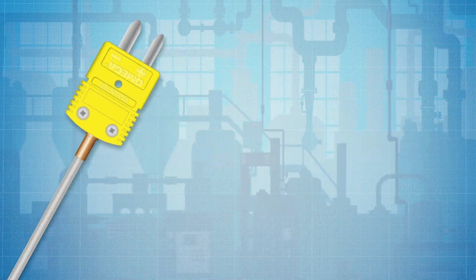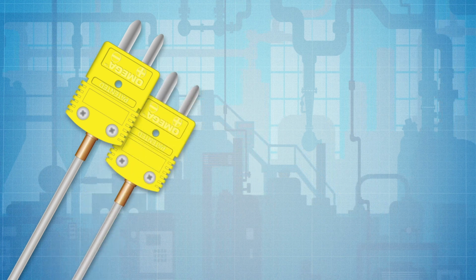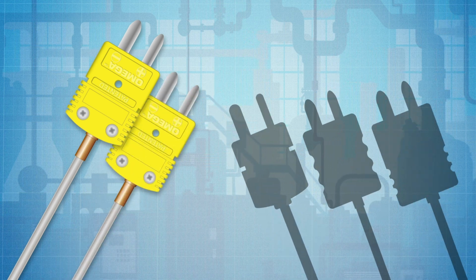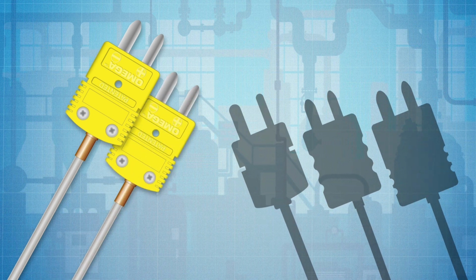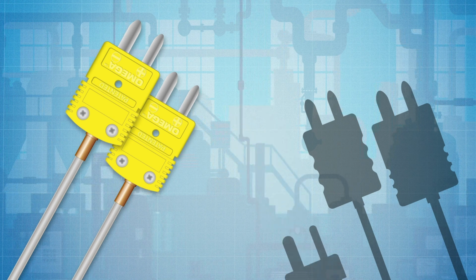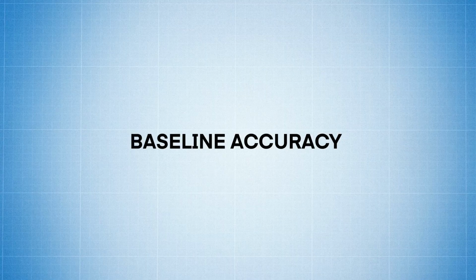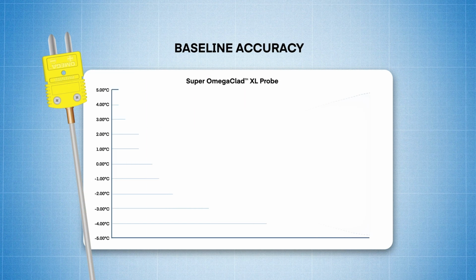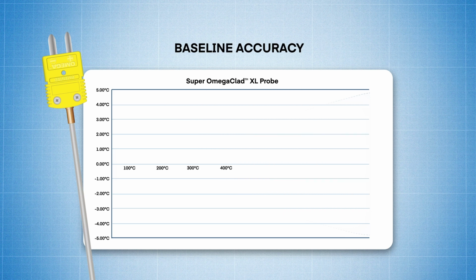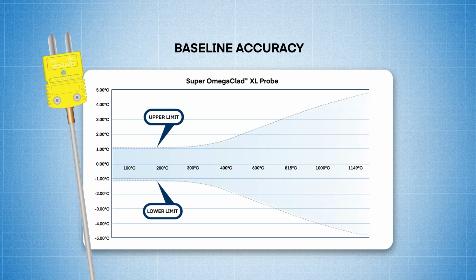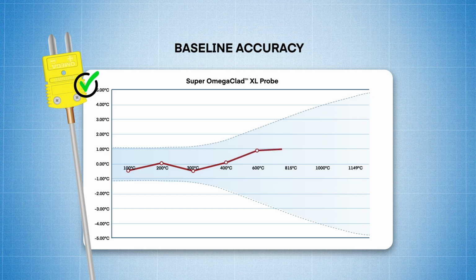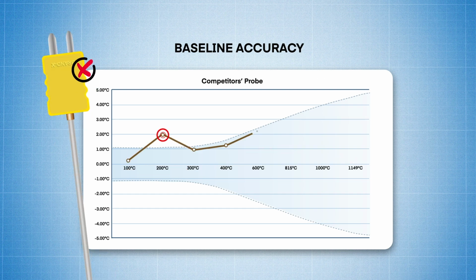To demonstrate, we put our Super Omegaclad XL and our standard Inconel probes up against some of our competitors' similarly spec'd probes in a battery of long-term tests, and the results speak for themselves. In baseline accuracy tests, we check the accuracy of 8 temperature points ranging from 100 degrees Celsius up to 1,149 degrees Celsius. And because DwyerOmega offers special limits of error at no additional costs on all our industrial thermocouple probes, our probes stayed solidly within tolerance, while the competitors' probes did not.